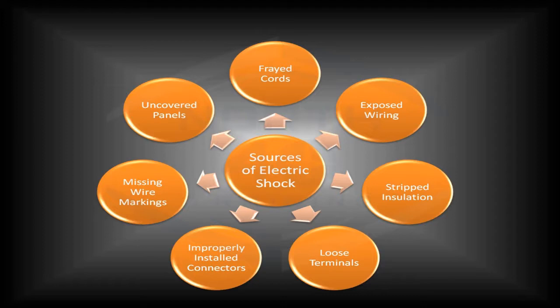Improperly installed connectors is another huge thing we see out on the job site from time to time. Maybe you've got the wrong temperature designation on the terminals for the job, or the wrong terminations, wrong connectors in general, or maybe they're double lugged. All of these things have to be taken care of because they can lead to tragedy, whether the building burns down due to additional heat created by improperly installed connectors, or somebody gets dangerously hurt. Loose terminals is another one.